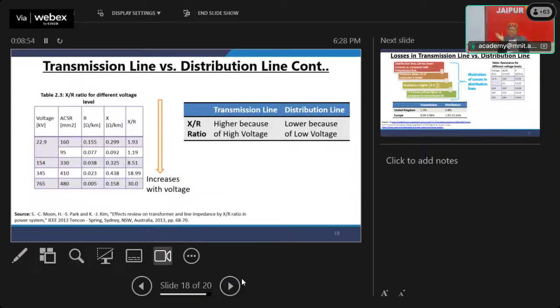Most of the power engineers in this country may not be very sure about what the X by R ratio is. Okay. So, what does it mean when the X by R ratio keeps increasing for high voltage? Whenever we draw a transmission network, we simply draw an inductor. We ignore the resistance because of this figure 30, because of this figure 20, because it is 20 times higher. The reactance is 20 times higher than the resistance component, and hence instead of RL we simply put an inductor.